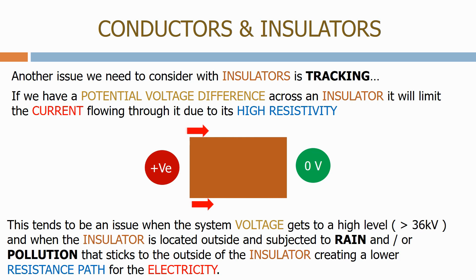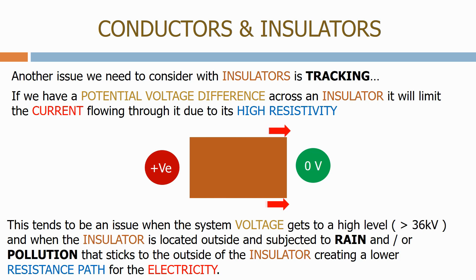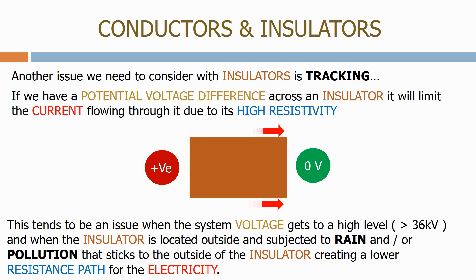This tends to be an issue when the system voltage gets to a high level, above 36 kV, and when the insulator is located outside and subjected to rain and/or pollution that sticks to the outside of the insulator, creating a lower resistance path for the electricity.